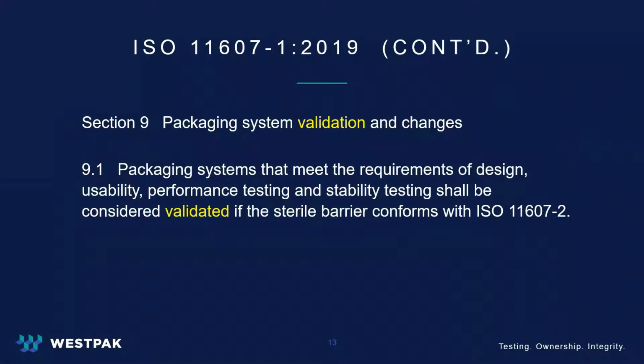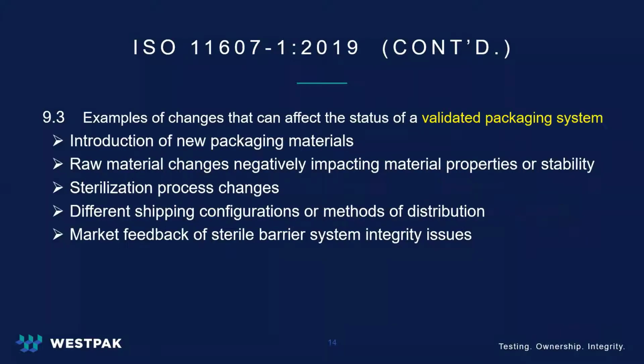Section 9 of 11607 defines the requirements for package system validation. You'll notice that if the sterile barrier being tested first conforms with the validation requirements per ISO 11607 Part 2 for forming, sealing, and assembly processes, and meets the requirements for performance and stability testing, the package shall be considered validated. A key point to understand is that a package validation is a combination of a full suite of test methods. Each of these test methods must be individually validated. Section 9.3 addresses any changes that can affect the status of a validated package system. The key takeaway from this section is that these examples, if they occur, may require a validated package system to go through revalidation.